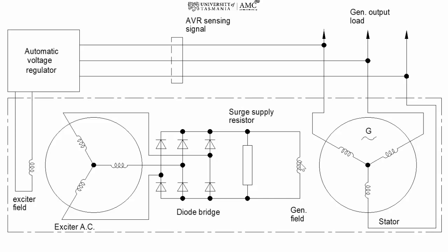These are on the rotor, and then in the generator we have stationary field coils around the outside. So we have 3 sets of windings or conductors, and from here we get our 3-phase voltage. 415 volts comes out of here and supplies through our distribution system through to our loads.